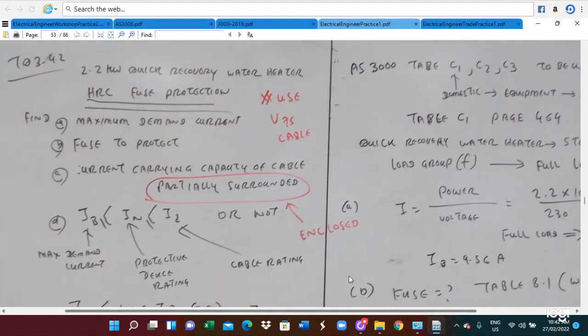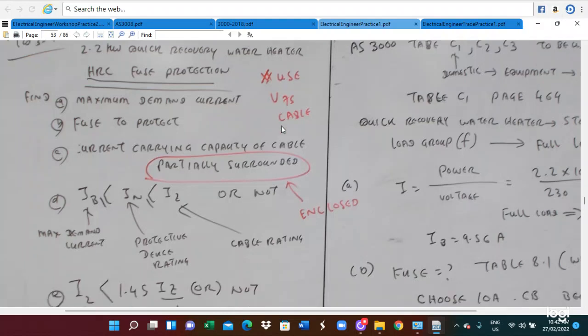The next problem involves a 2.2kW quick recovery water heater. We need to find the HRC fuse protection rating and the current-carrying capacity of the cable, which is partially surrounded by insulation. The protection coordination formula is: IB ≤ IN ≤ IZ, where IB is the maximum demand current, IN is the protective device rating, and IZ is the cable current-carrying capacity.